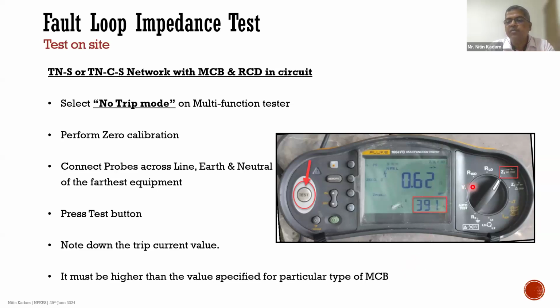Now, why does this have to be done in the no trip mode? If there is an RCD in the circuit of a TNS or a TNCS network, what happens is if you do this test in the high current trip mode, the RCD will first trip and will not allow you to complete the fault loop impedance test. So therefore, this has to be done in the no trip mode so that the RCD does not trip, the MCB trips, and you get the values here.